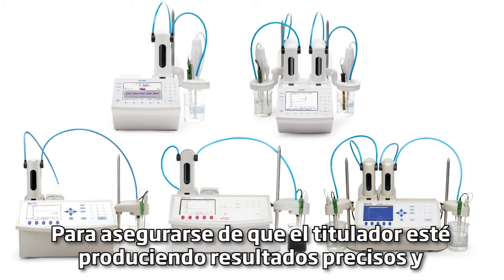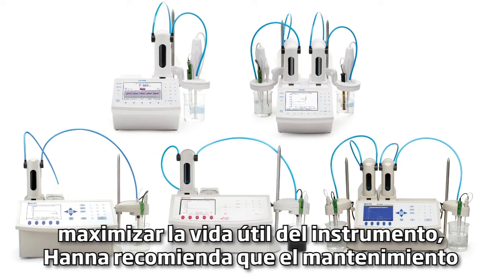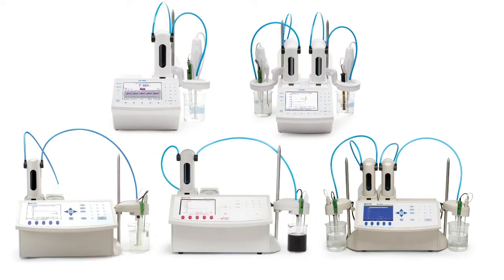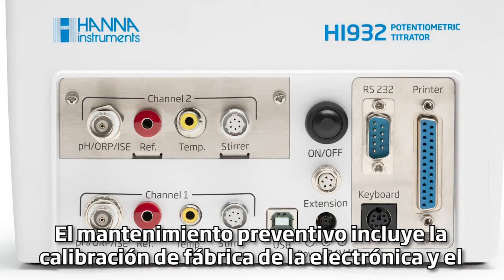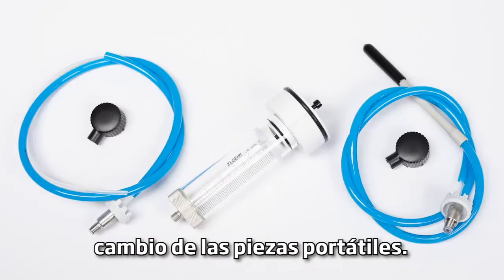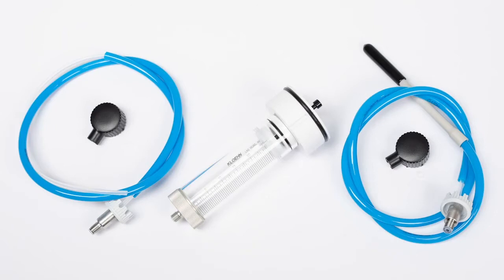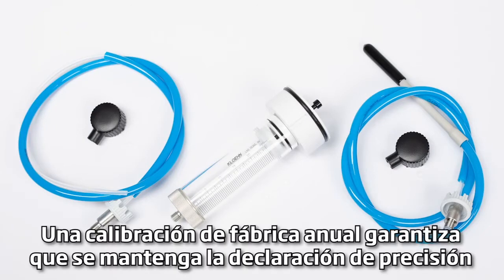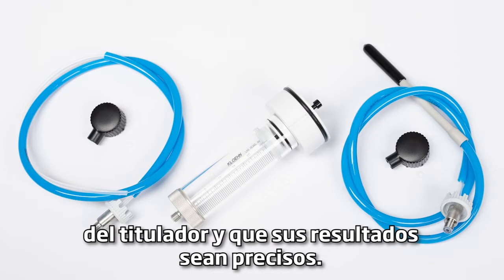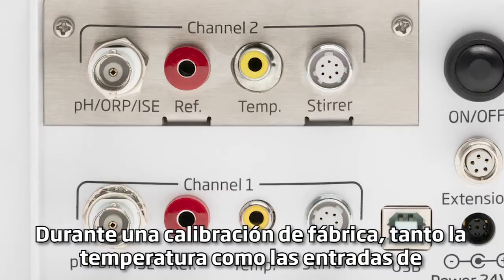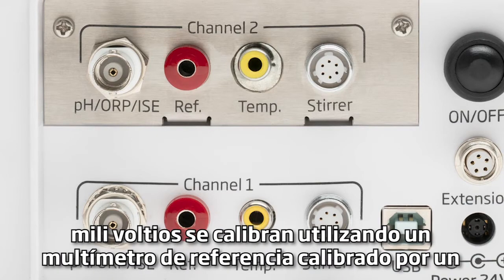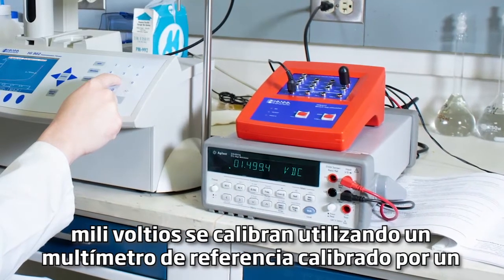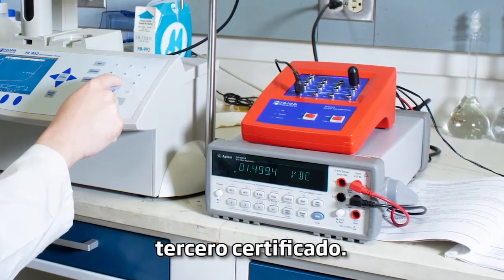In order to ensure that the titrator is yielding accurate results and that you're maximizing the life expectancy of the instrument, Hanna recommends that the preventative maintenance be performed annually. Preventative maintenance includes the factory calibration of the electronics and changing of the wearable parts. A yearly factory calibration ensures that the accuracy statement of the titrator is maintained and that your results will be accurate. During a factory calibration, both the temperature and millivolt inputs are calibrated using a reference multimeter that is calibrated by a certified third party.